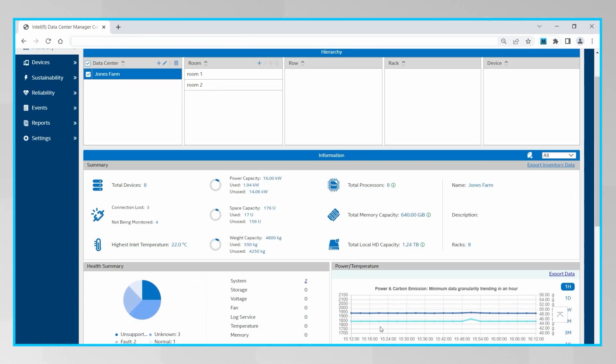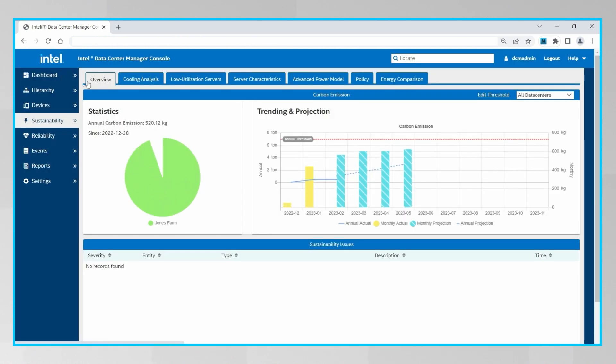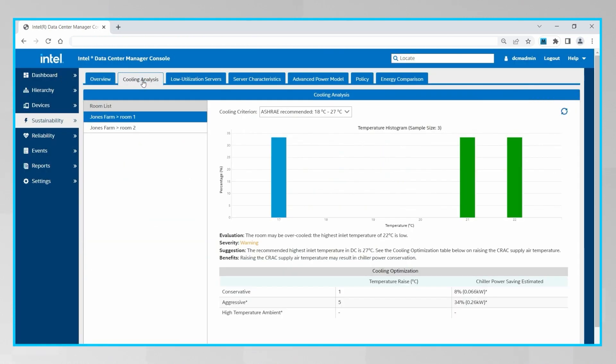Another action we can take is click on the sustainability tab and look at the cooling analysis to see if we are unnecessarily overcooling some of the rooms in our data centers. If most of the servers in a room are running cold, it might be a good opportunity to safely increase the set point temperature to reduce the energy spent on cooling. This is not really the case in this room in particular, but it was very easy for us to verify that.